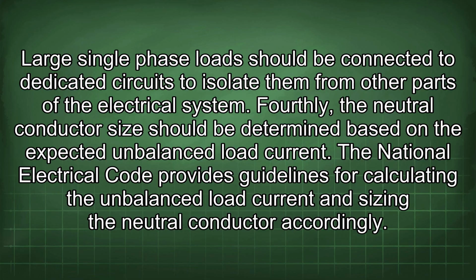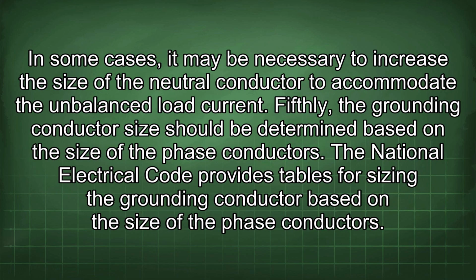Fourthly, the neutral conductor size should be determined based on the expected unbalanced load current. The National Electrical Code provides guidelines for calculating the unbalanced load current and sizing the neutral conductor accordingly. In some cases, it may be necessary to increase the size of the neutral conductor to accommodate the unbalanced load current. Fifthly, the grounding conductor size should be determined based on the size of the phase conductors.